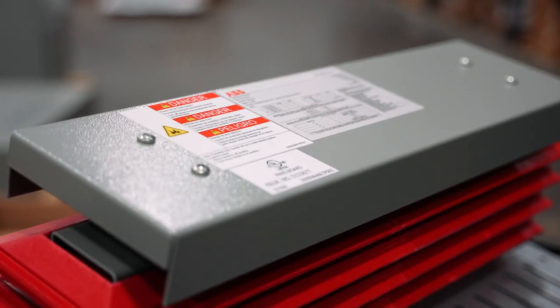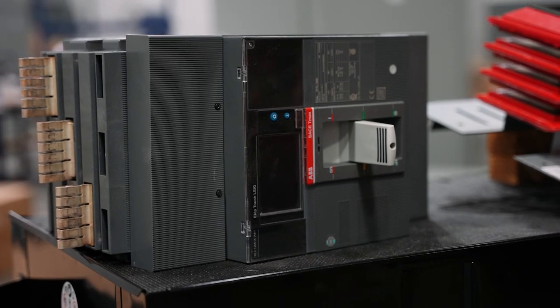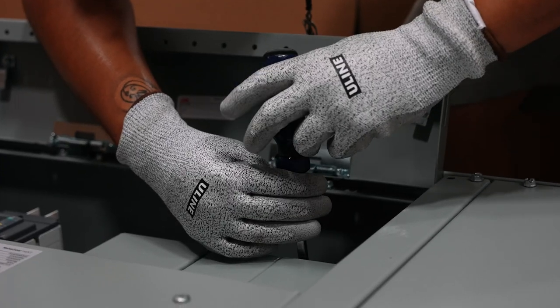At Lone Star, we've invested over a million dollars in this Superbox power panel inventory, and the range is pretty impressive. ABB has made the program available from up to 1200 amps and down to 600 amps and everything in between. Because of the configurability of the breakers, with long time, short time, and instantaneous trips, this allows a 1200 amp breaker to be used in 1000 amp, 900 amp, and multiple other configurations.